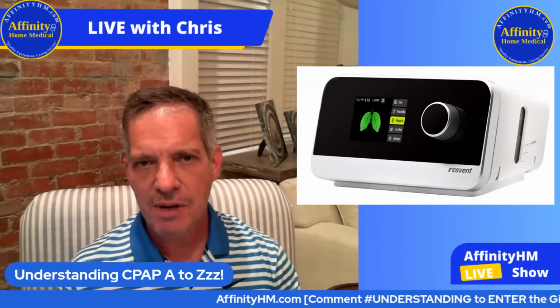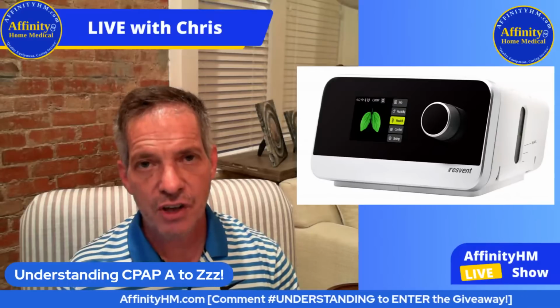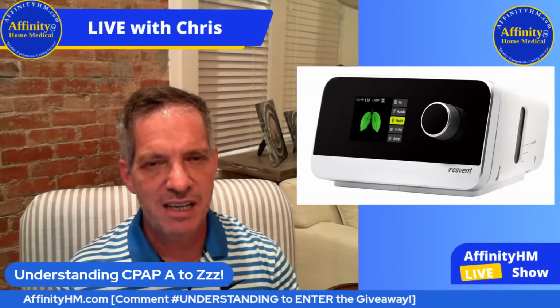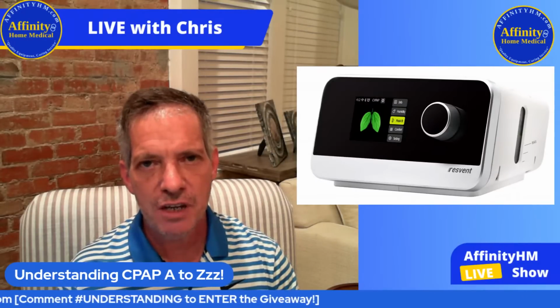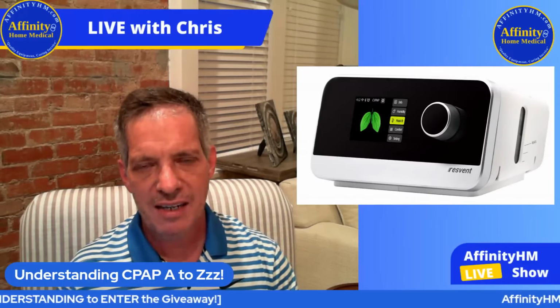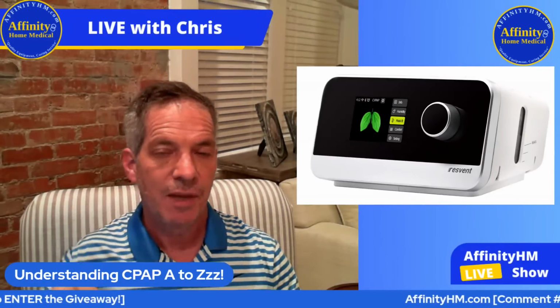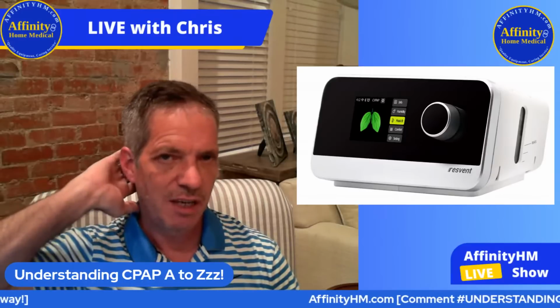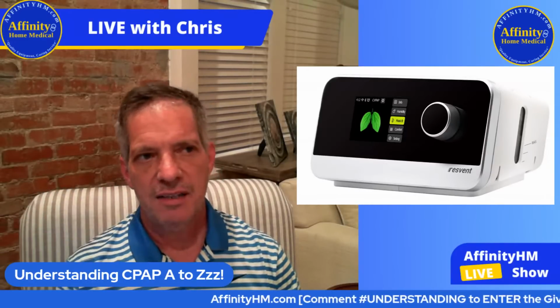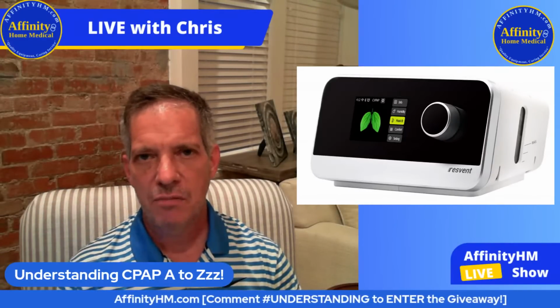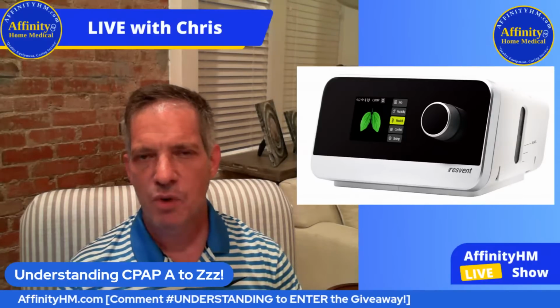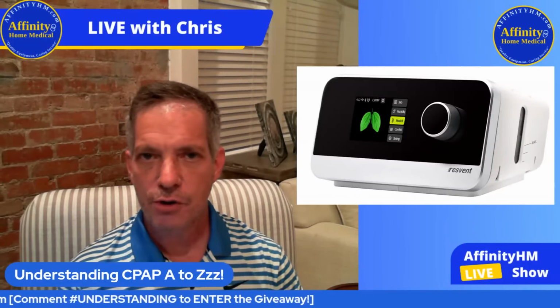But with the central apnea, a BiPAP can also, you've heard them called ASVs, it also has an additional feature so that a backup rate can be set in the machine. For example, if that brainstem is not triggering, then let's say you're breathing 20 times per minute. Normally, everything's fine, but we set a backup rate, say the doctor ordered 12.